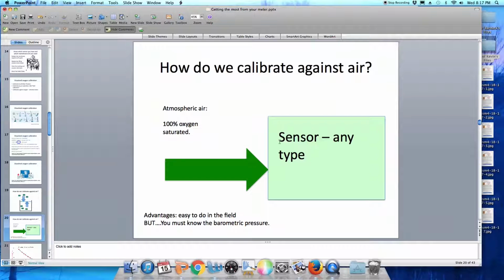So what we do is we put the sensor in the atmosphere. The atmospheric oxygen forces its way through the membrane. And again, we say that the oxygen is 100% saturated. So when the oxygen from the air is forcing its way through the membrane, we know that the percent saturation is 100%. There cannot be any more oxygen than there is in the atmosphere. Now, the advantage of this field calibration is that it's very easy to do in the field.